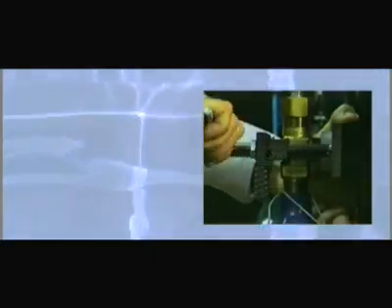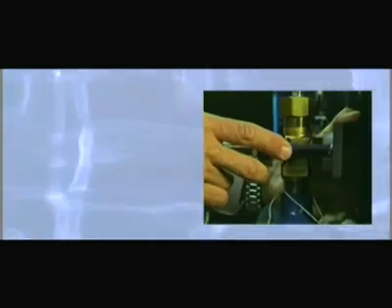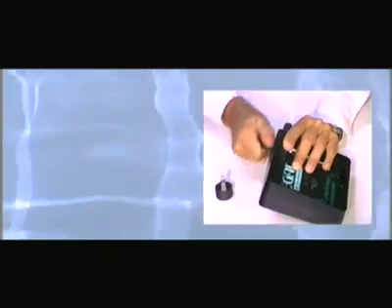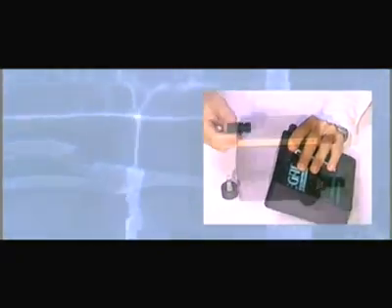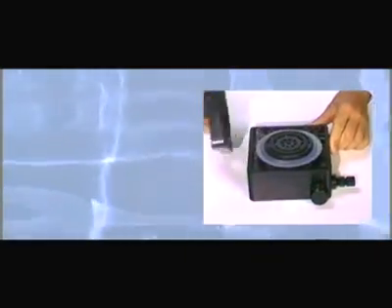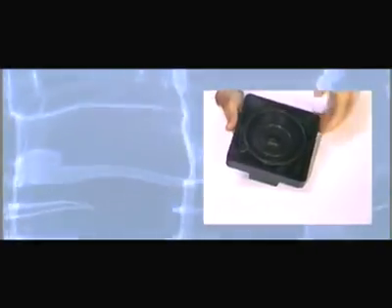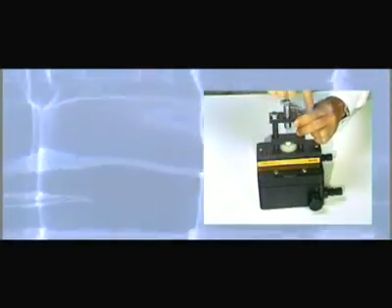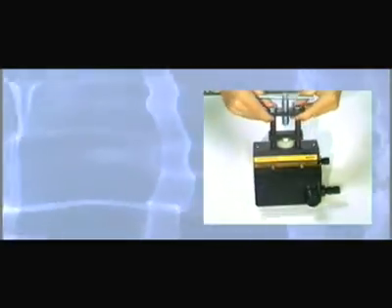With the cylinder valve closed, the unit can be safely removed from the tank. In normal operation, the chlorine gas is never under pressure in the Regal system. Comprised of far fewer parts than competitors, the regulator can be disassembled with only a screwdriver and pliers, serviced and reassembled quickly right on site. All parts are specially designed to be corrosion resistant in a chlorine gas environment. Components are engineered to withstand stresses far greater than encountered in actual use.